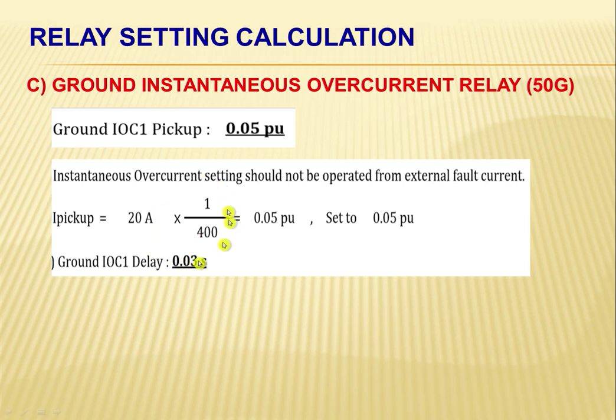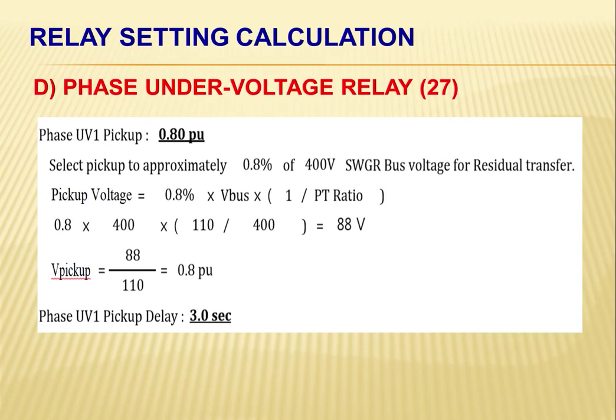So, multiply by the ratio of our zero sequence current transformer, which is 1 over 400. So our setting will be, the ground IOC pickup will be 0.05 per unit. Since this is instantaneous, our ground instantaneous overcurrent delay will be 0.03 seconds. Next, we will be discussing the phase under voltage relay.